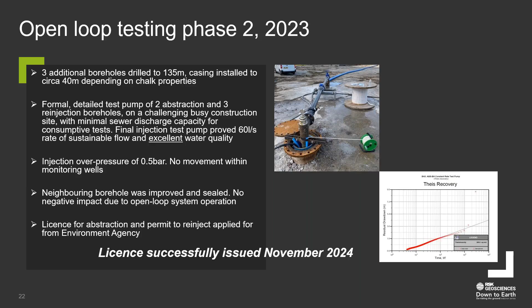Next slide, please. So in conclusion, this is an excellent system. The performance of the system is great. It's able to provide the full peak that they wanted of 1.5 megawatts. The presence of that superficial clay layer was vital to this particular application. Also, the presence of known soil contamination from previous industrial use wasn't an issue. That was managed by design and by borehole construction methods. The 5 boreholes were drilled, completed, tested, and all plumbed into the district heating system on a very busy construction site. Not easy, but it can be done.